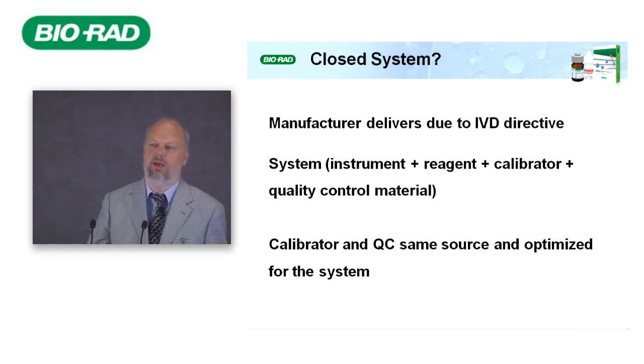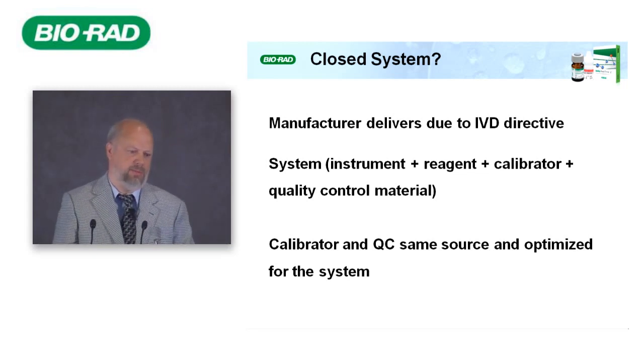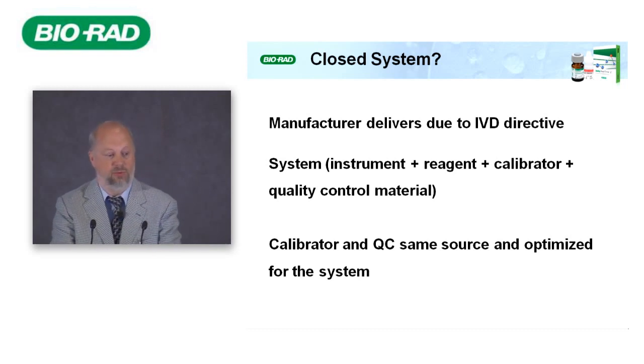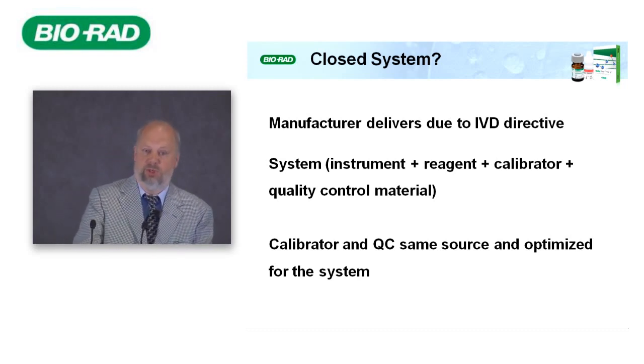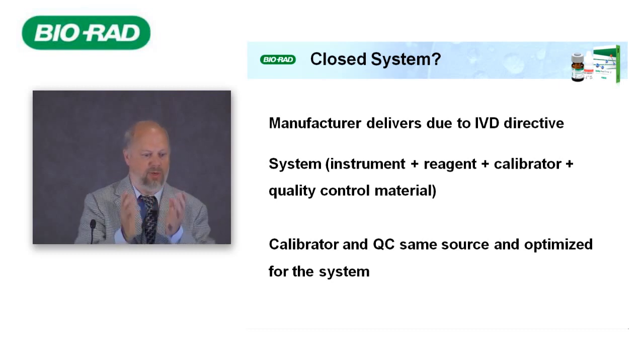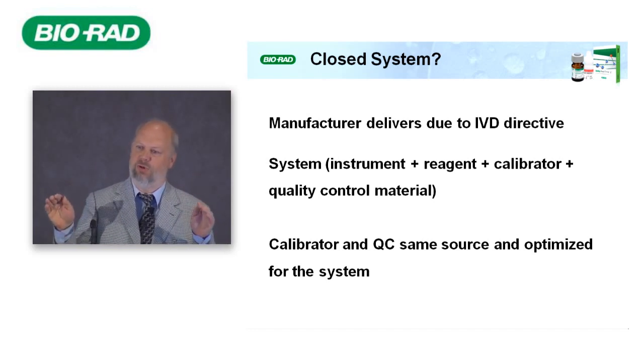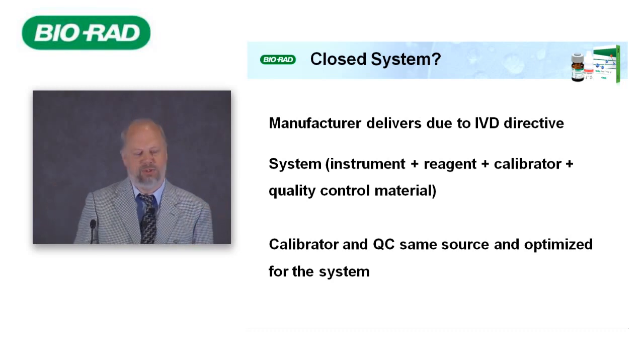Today we have mainly closed systems. The manufacturer delivers — due to the IVD directive regulations — the system: the instrument, the reagent, the calibrator, and the quality control. You have a totally closed system. And sometimes the manufacturer adjusts their quality control material to match the calibrator, so you believe you are in a very safe situation.